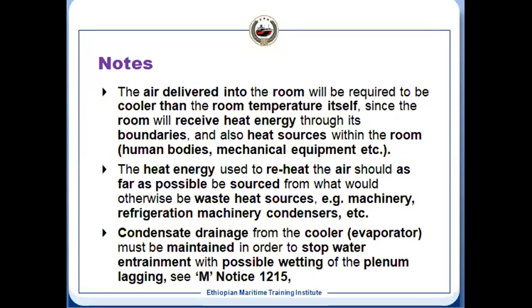and then it goes to the cabins. So that is the way its actual process works. The air delivery in the room, as I told you, should be cooler than the room temperature we want to maintain, because of the heat. The human body also releases heat. Mechanical equipment, definitely there will be some equipment in the room which will be in use. Suppose you have a refrigerator, that also is releasing heat energy. So to cancel it out, we need to supply lower temperature air.